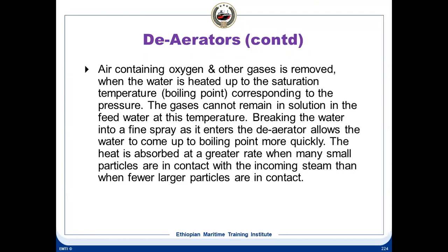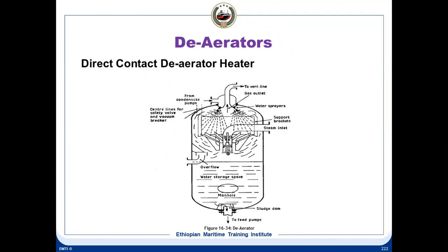And then here what we do is break up the water into a fine spray. So this feed water which is coming in is broken up into a fine spray. The reason is the same as earlier, like we studied for the burners: the fuel is broken up into a very fine spray, the fuel is atomized. Here also the feed water condensate is broken up into fine spray so that its surface area is improved.